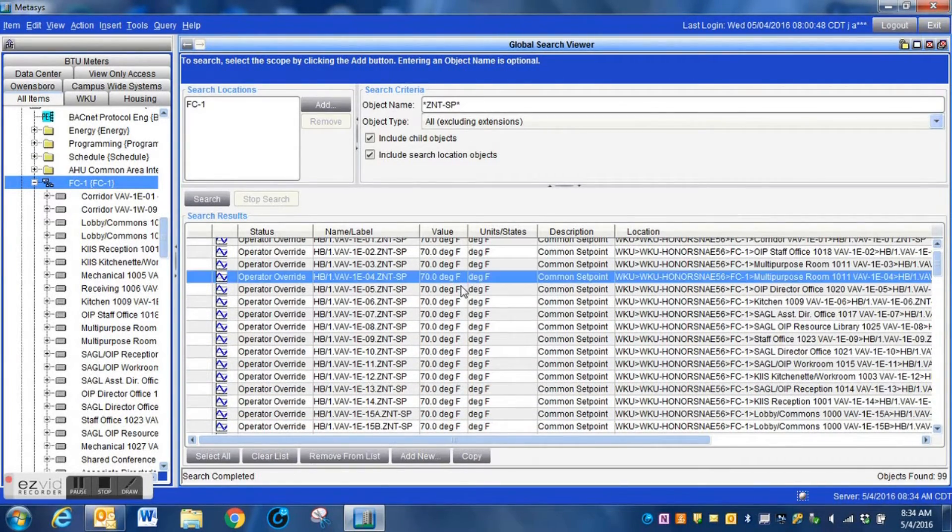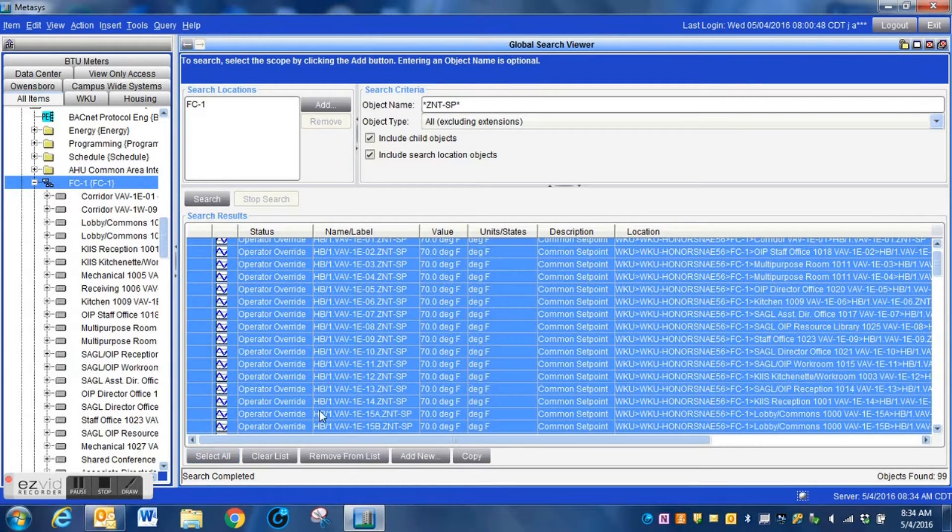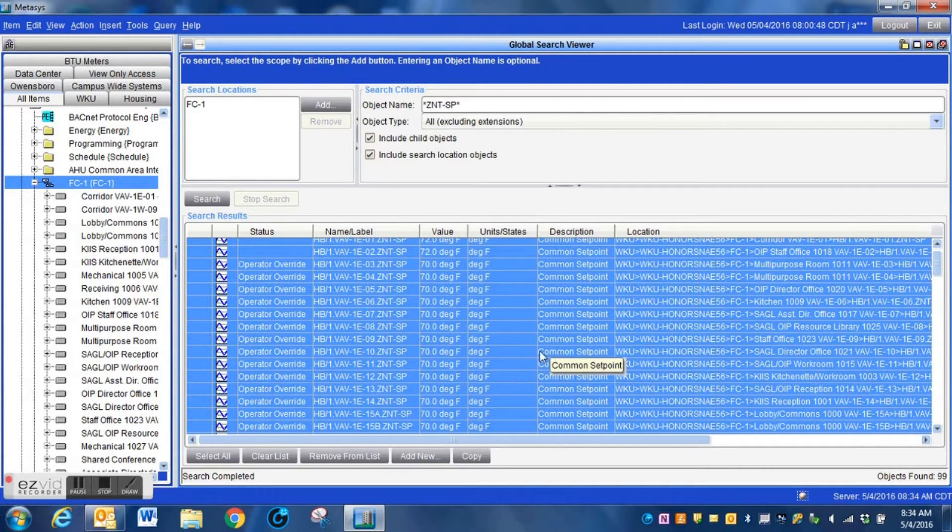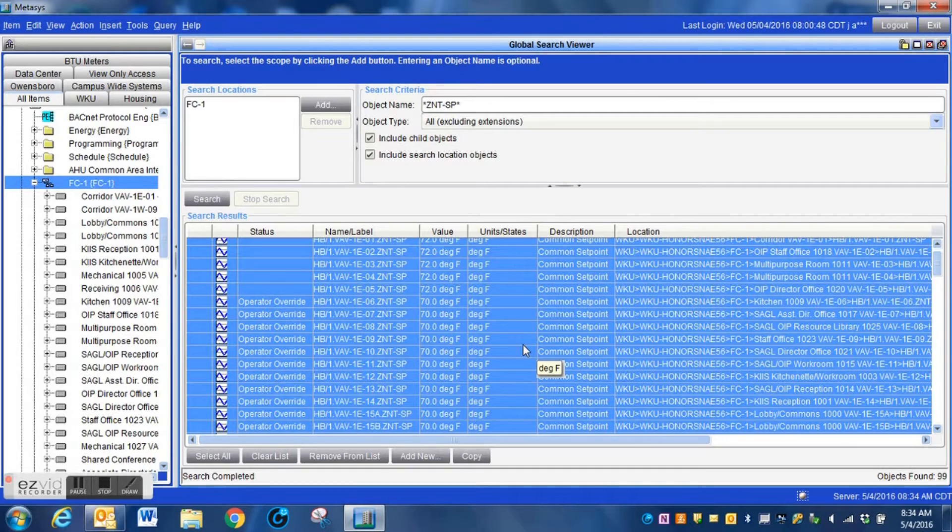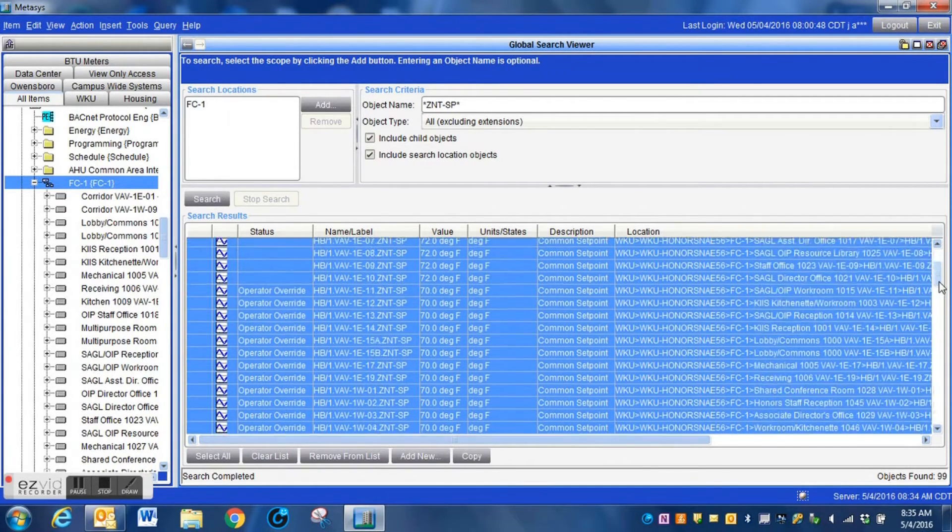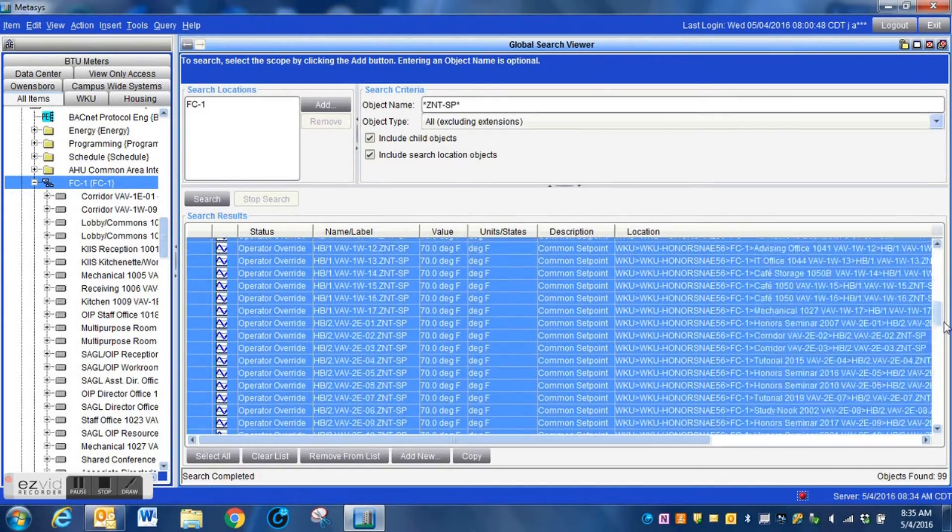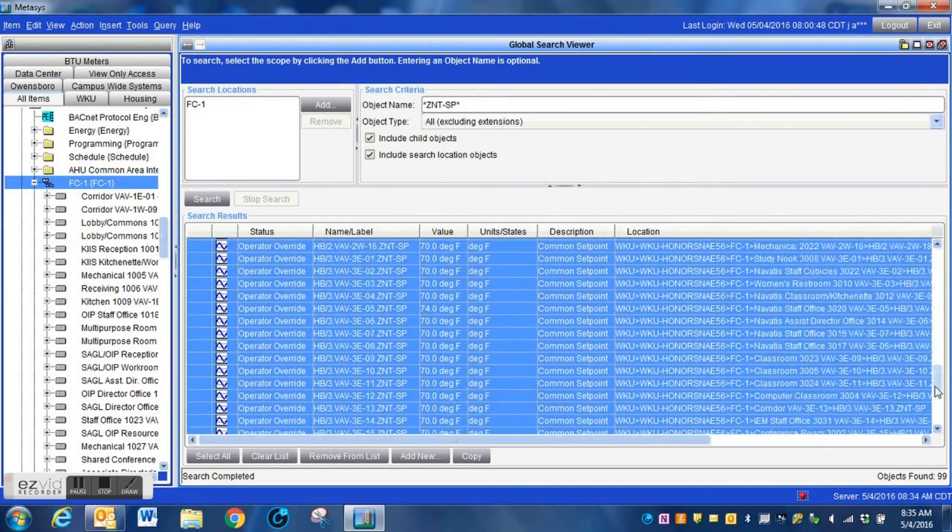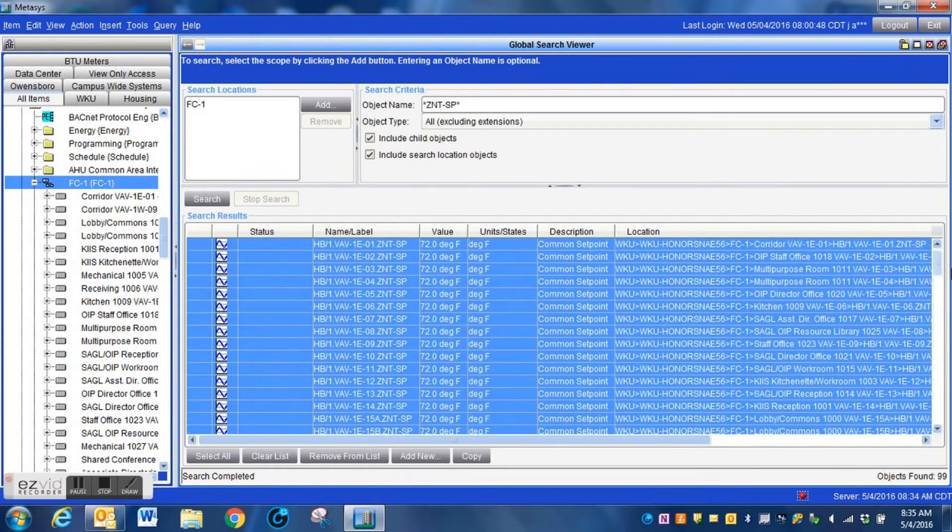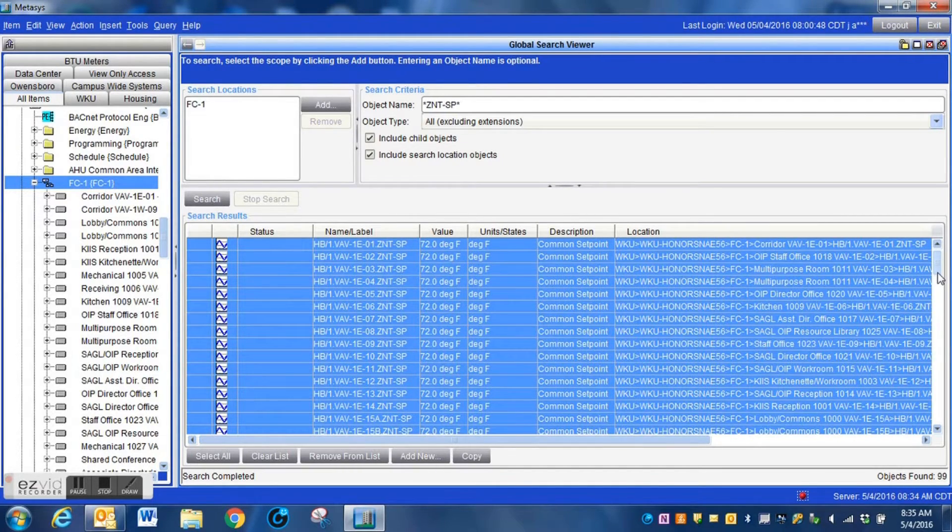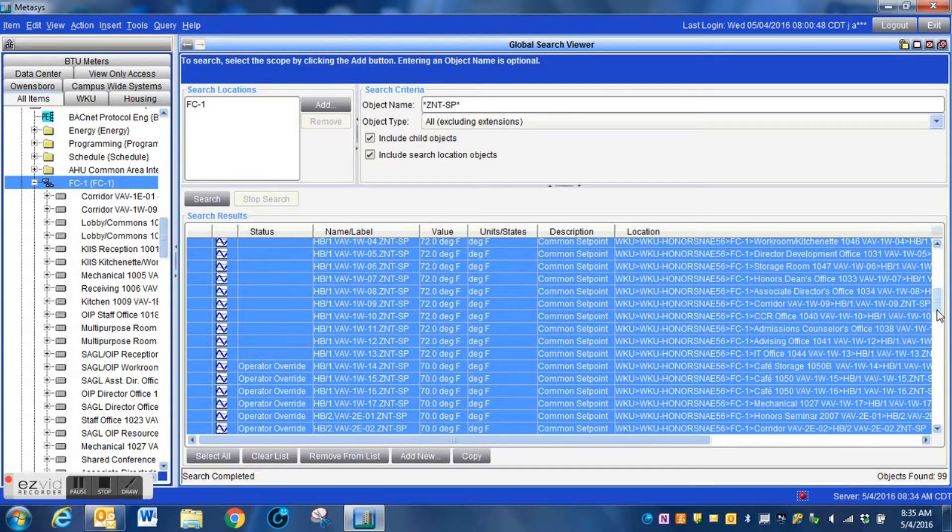That is one way that can be used to change an entire building set point. If you have an entire building that you run, you do adjustments of set points seasonally, which is common in some areas. What we're doing here is we're just releasing the overrides that are on all of these set points here. When you create a list like this within the global data search, when you command those points, it will take just a little bit of time for the command to get out to all of the devices.